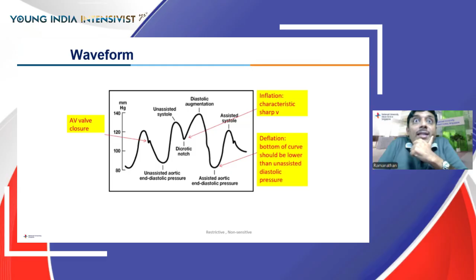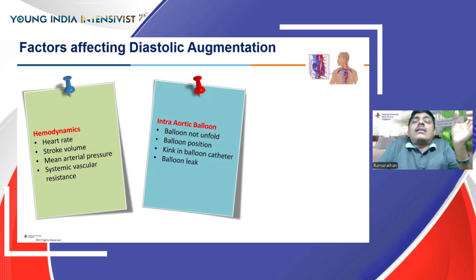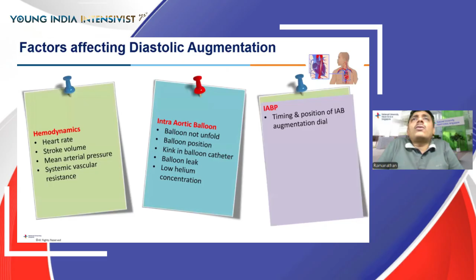Now, there are certain factors that affect diastolic augmentation. Clearly, the patient's hemodynamics make a big difference. If your patient is tachycardic, the augmentation can be poor. Then there are factors related to the machine that may affect diastolic augmentation. As we saw in that X-ray earlier, a kink in the balloon catheter, or low helium concentration, affects the diastolic augmentation. And of course, not timing or positioning the balloon pump properly also impacts diastolic augmentation.